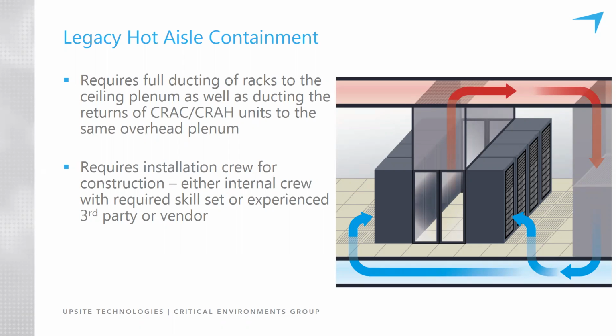But the downside of, well, I'll talk about the advantages of hot aisle containment, which is, in this example, we're looking at hot aisle containment. And so if you're fully containing the hot air, then the rest of the room becomes cold. And the placement of supply tiles is not as critical. The air is free to flow around in the room and make its way to where it's needed. So the room feels cool. The airflow is managed a little easier. Any leakage of conditioned air through the raised floor, as long as it's not under a cabinet, goes into the general space for cooling. And so hot aisle containment tends to be more efficient because it tends to be done more effectively.